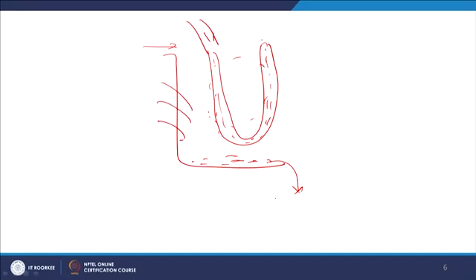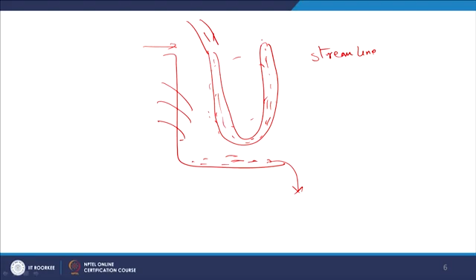This is used when the coal has low volatile material. When the coal is low volatile, this type of burner is recommended. Here the formation of ash takes place and subsequently the ash can be drained off or removed from the system. So, this is the long flame or U flame type, and it is also called a streamline burner, right.